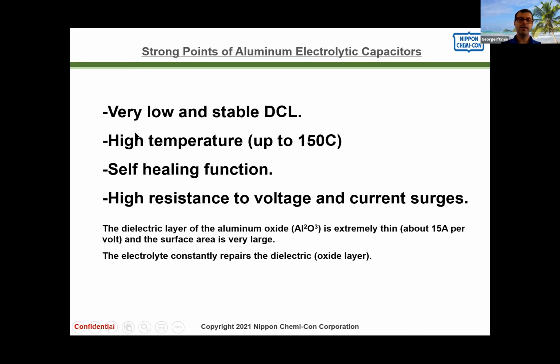Another strong point, leakage current is very low and very stable, at least for our capacitors. I've seen data for some competitors which is not so good, but that's very important. You want consistent performance from the capacitor. And of course, leakage current is what consumes the electrolyte, so having high leakage current will almost always translate into a shorter life.